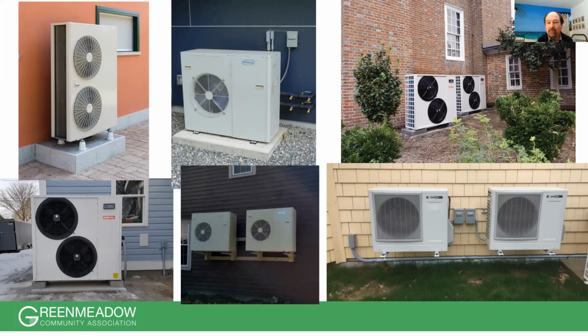Unlike a boiler, which can provide the same amount of BTUs year round, these heat pumps are ambient air driven. So at the same time when we need more energy in the house, it's also the coldest time of the year, so we have to size it for the worst case scenario. Sometimes we will use a backup element type system to supplement it, but preferably without it, so we take advantage of the high performance of these heat pumps, which is anywhere between 2.5 to almost 5 COPs.